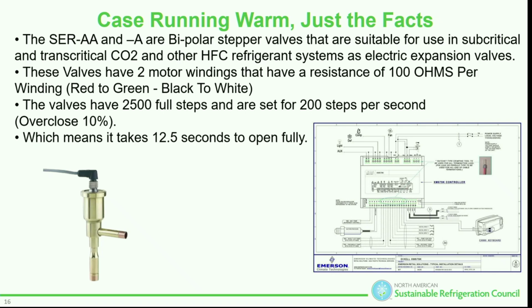The valve has two motor windings that have a resistance. On this particular type of motor, they have 100 ohms per winding, and that's from red to green and black to white. There are some different manufacturers that have different resistances, and same thing with the next thing I'm about to tell you. This valve in particular has 2,500 steps from open to close and is set for a step rate of 200 steps per second. That means that going from 0 to 100%, that valve should essentially take 12.5 seconds to fully open and also fully close.